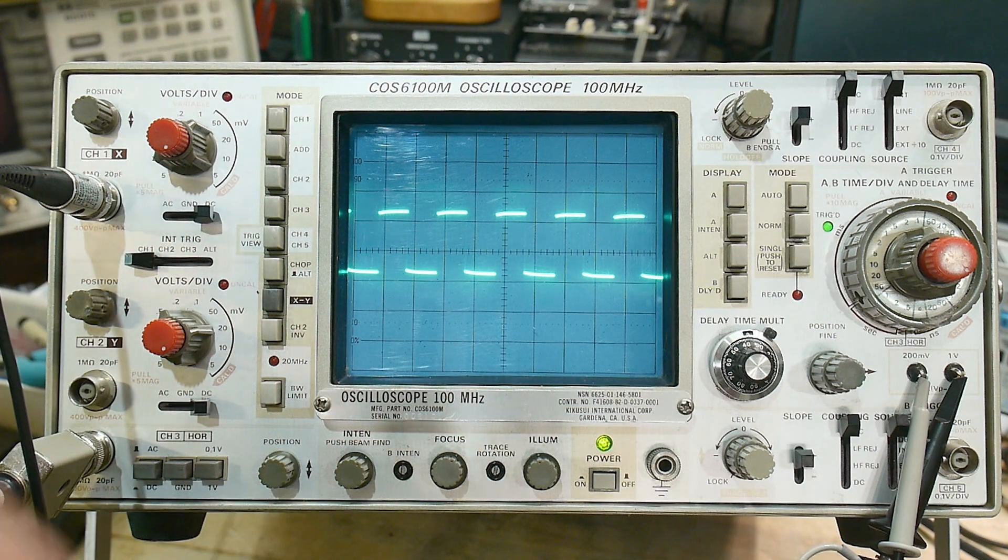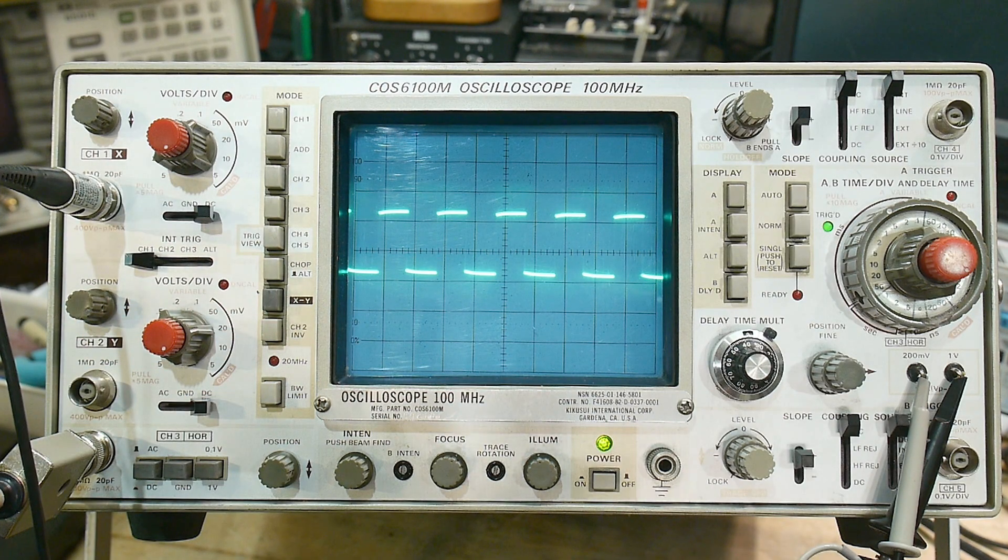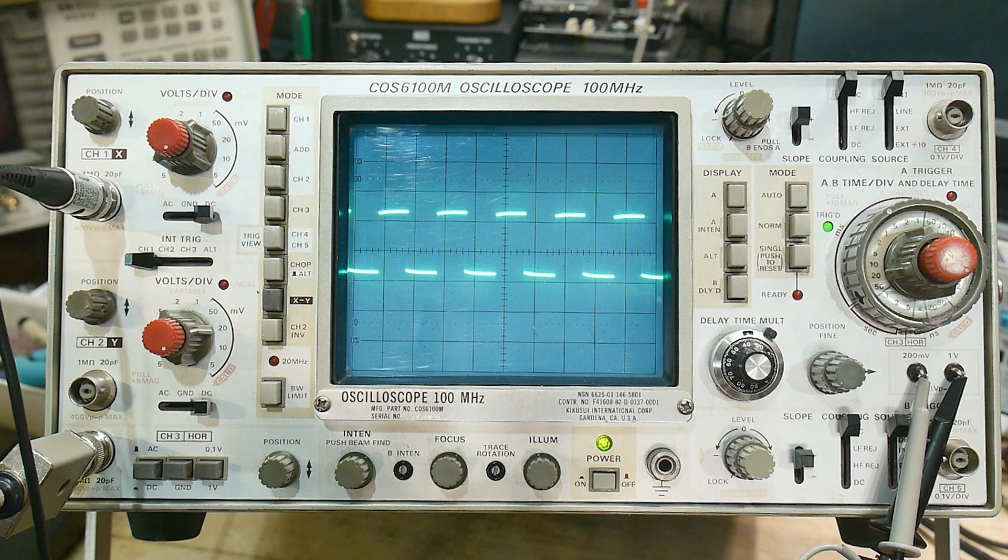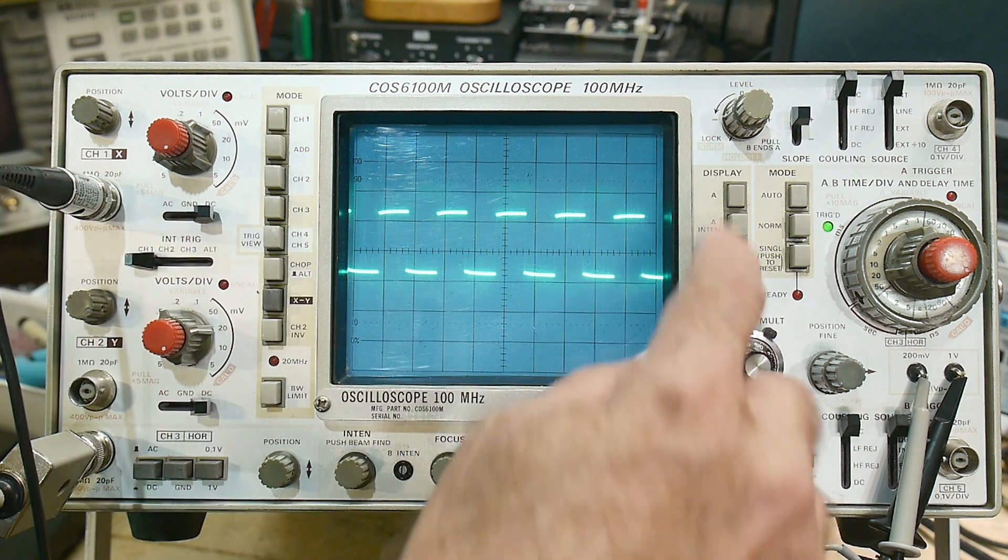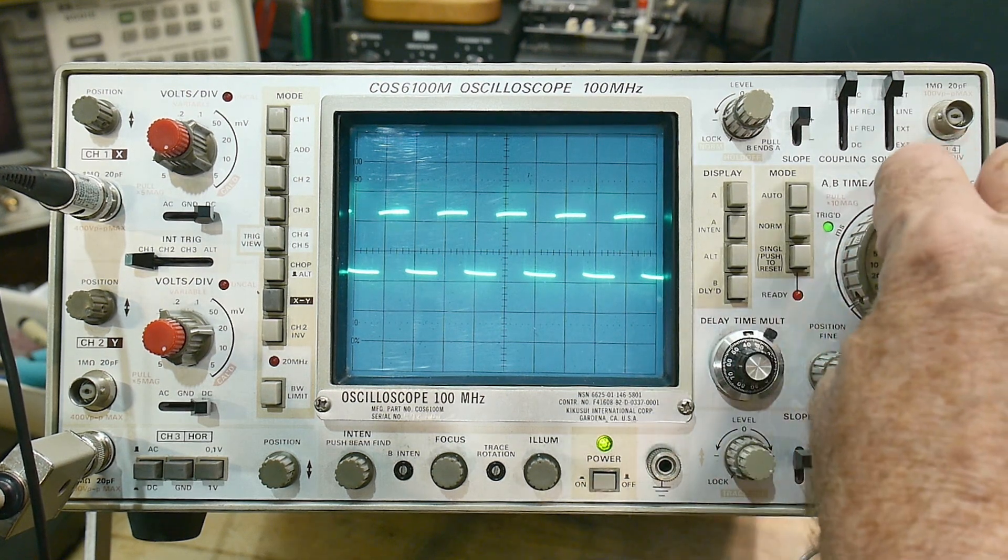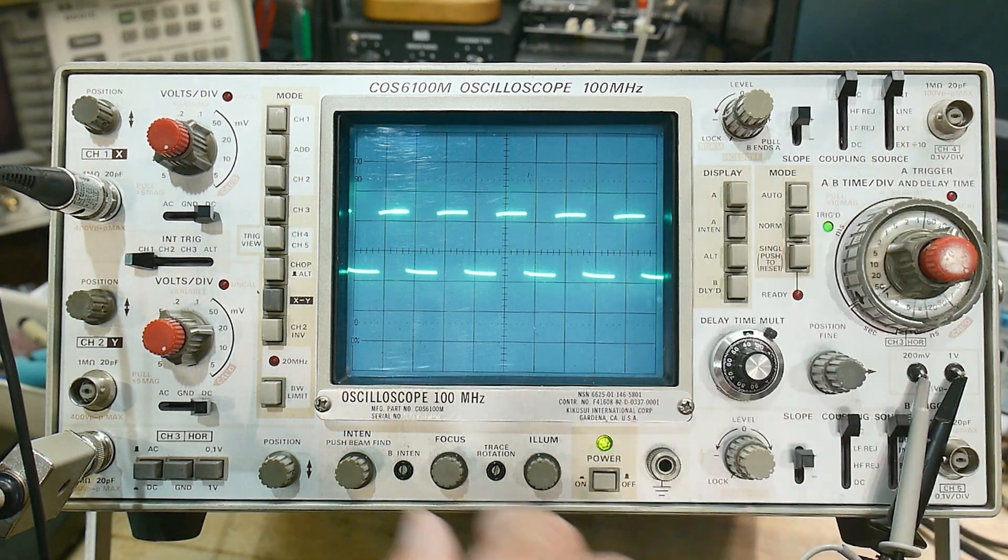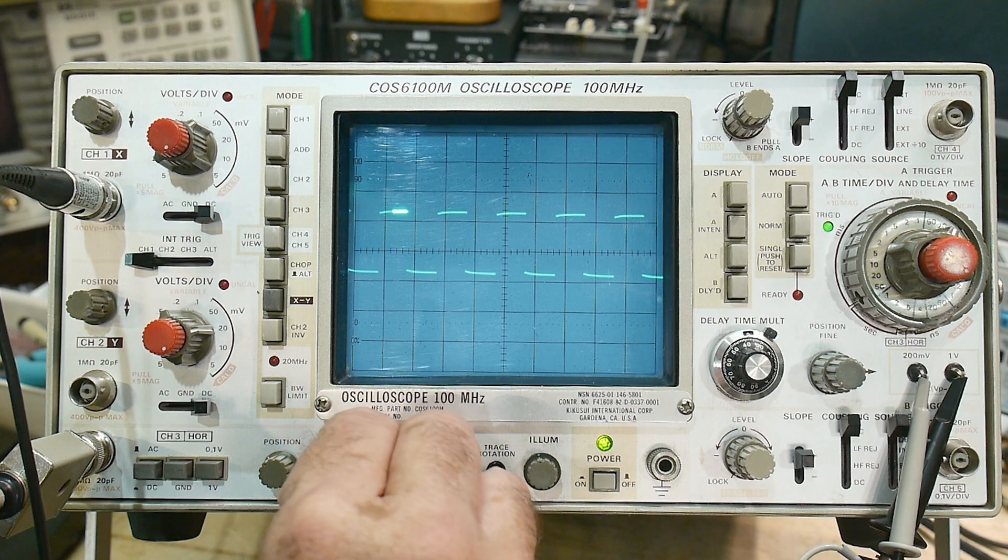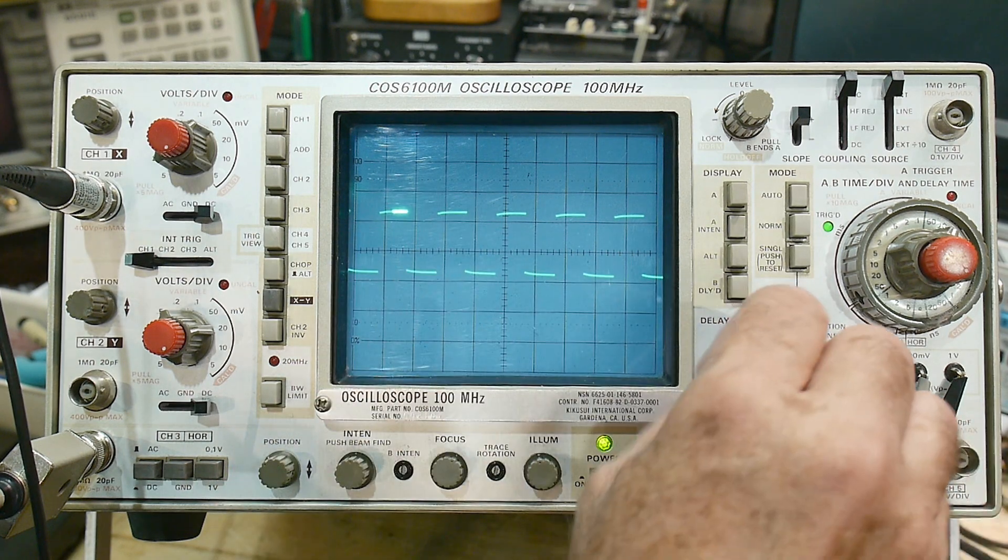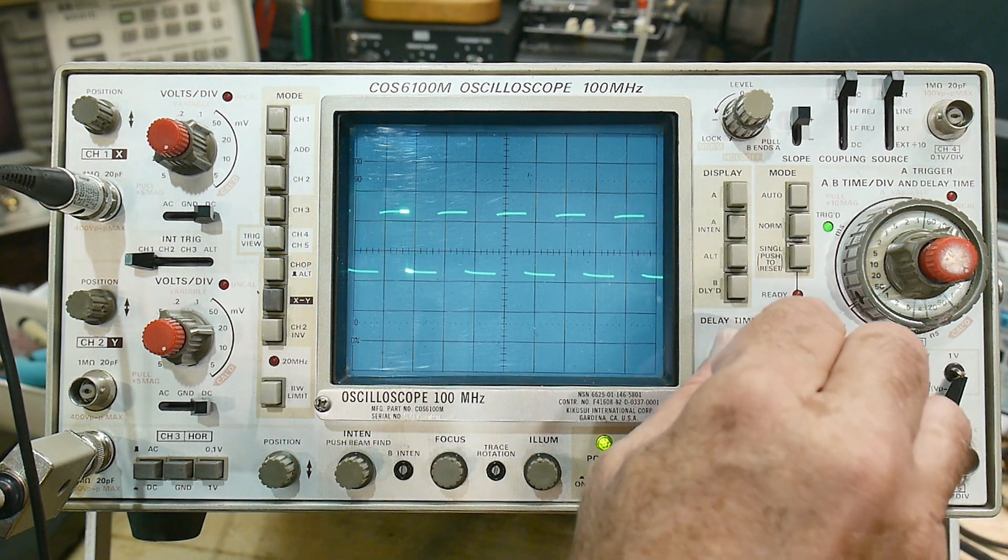It's pretty nice, it does have delayed sweep. I was going to do a whole video on delayed sweep, but I'll give you kind of a quick view of that. We can go to A intensified by B, and let's turn down the intensity here. You can see this little bit here that's intensified, right?